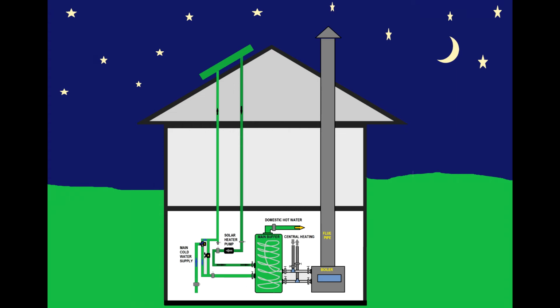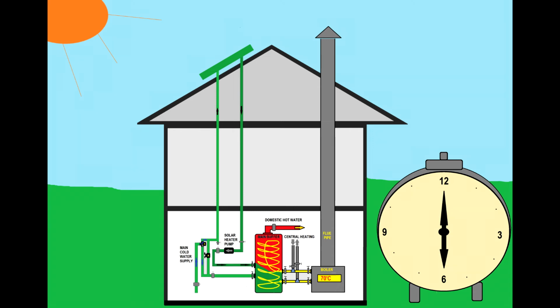Imagine it's nighttime, and we already have the main buffer preheated. That main buffer has the capability to retain some energy, so we keep the water hot until the morning. But this is mostly for domestic use, where you're not using an excessive quantity of water. In the morning, say at 6 o'clock when you go to work, you'll use the boiler to heat the water if you have a store, a manufacturer, or a shop, because you use a large quantity of water and consume the hot water left overnight immediately.